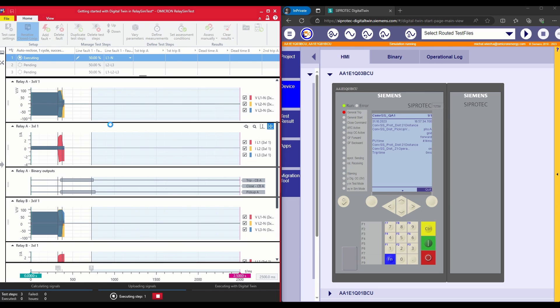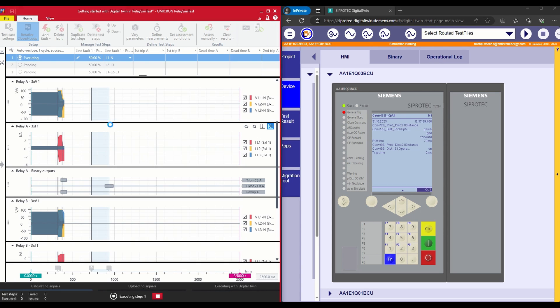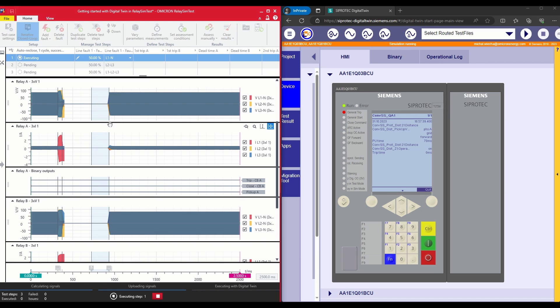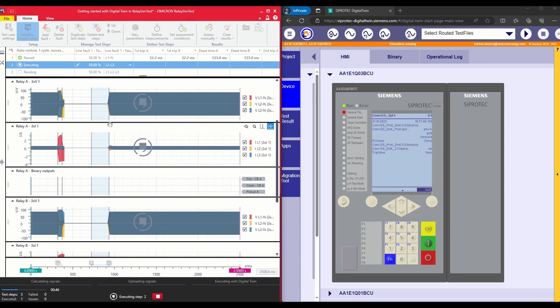As we can see, digital twin relays are responding to simulated relay sim test signals. And relay sim test receives the feedback pickup, trip and close signals as well.